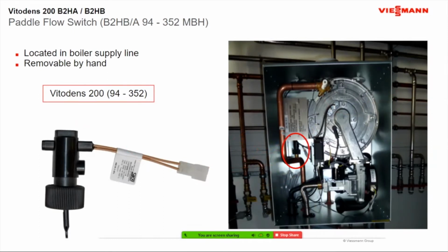You can check these with, it's just an open and close switch. Or if you want to see if your boiler is activating, if it's not going for some reason, you think everything's working right, you can jump out the plug going to the flow switch, the boiler should fire. And then you know that you're having an issue with your flow switch. And sometimes it could be just a matter of something's got stuck under the paddle, like a solder ball.